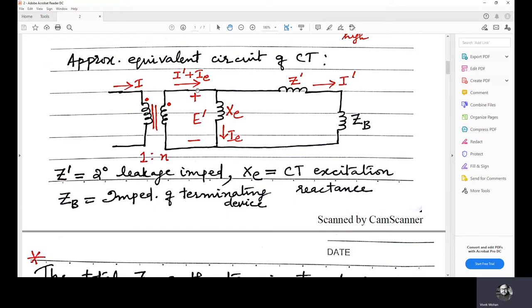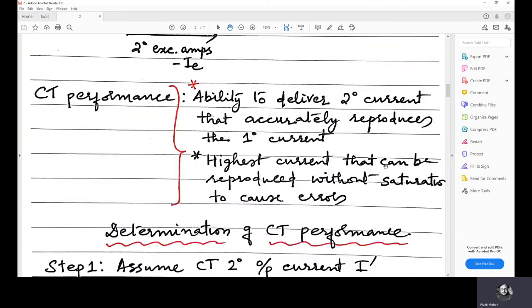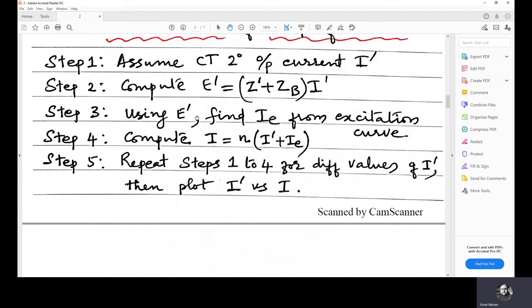i' plus ie is the actual secondary current; from this, ie is detected which is the excitation current, and i' is only seen by the relay. If there is a big difference between i' and i' plus ie, then i' may not reflect the actual fault current i, because the secondary current should reproduce the fault current at a scaled-down level. If that is not happening, the protection system will not operate properly — so that is what we are trying to analyze.